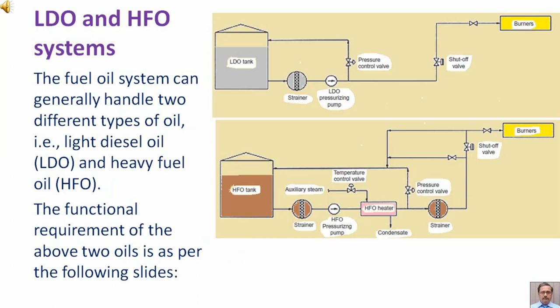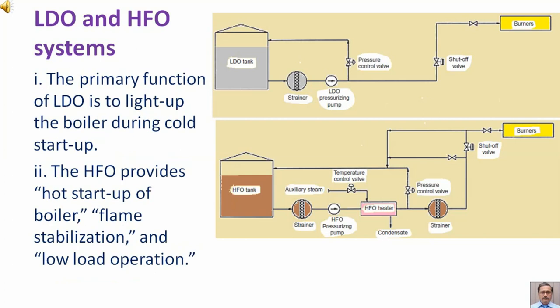The fuel oil system can generally handle two different types of oil: light diesel oil, also called LDO, and heavy fuel oil, also called HFO. The primary function of LDO is to light up the boiler during cold startup. HFO provides hot startup of the boiler, flame stabilization, and low load operation.